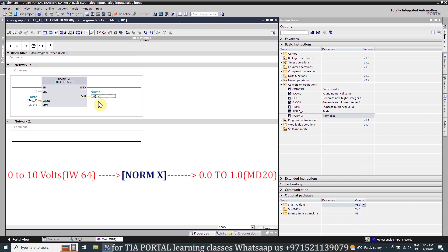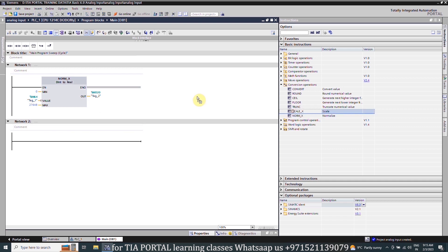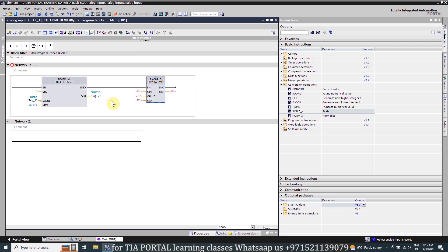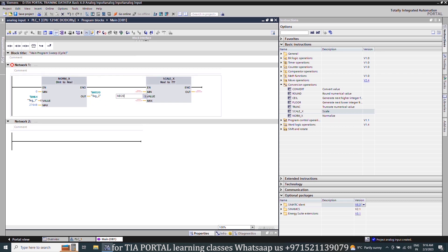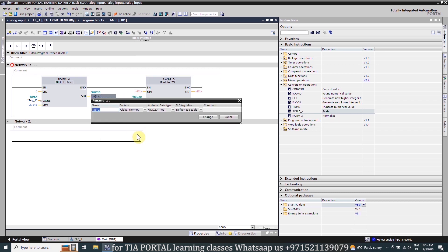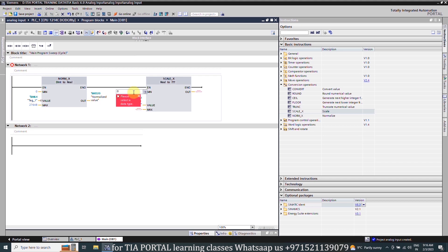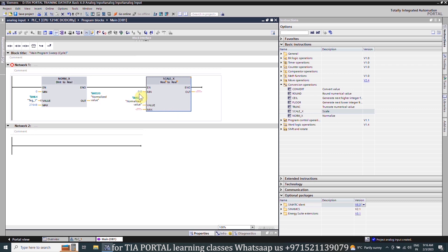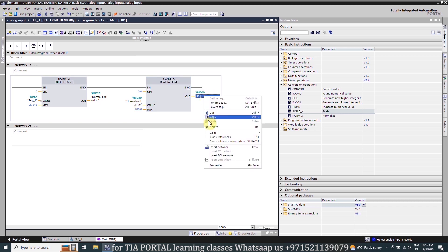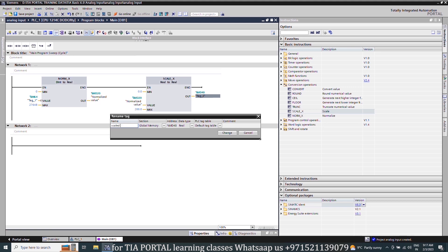Next we will drag and drop the SCALE_X function. For input value we will again select the real data type and we will use the same MD20 data register as a value input. We can rename the MD20 data register as normalized value so that it is more understandable. In the minimum value we will insert 0.0. Right now it is giving some error. To solve this we have to select the output data type as real as well. Next we will insert the max as 200.0. In the out we will insert the MD40 data register, and we can rename this data register MD40 as scaled value.